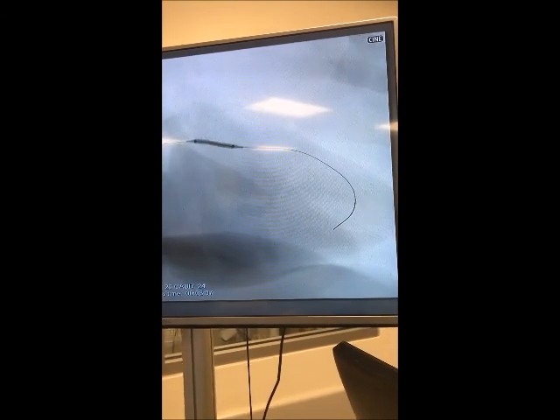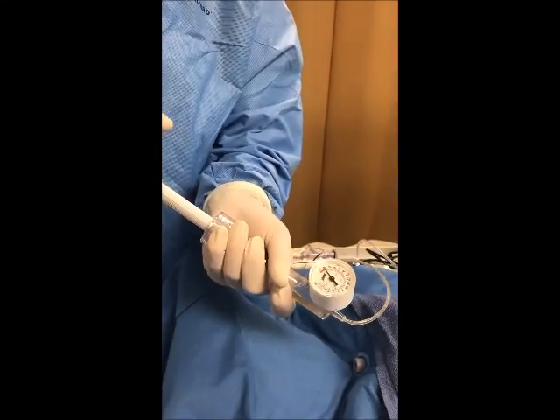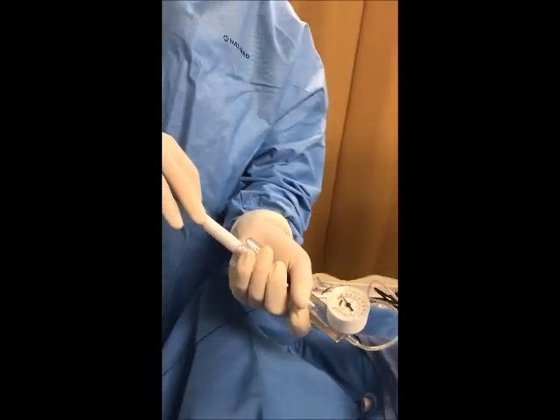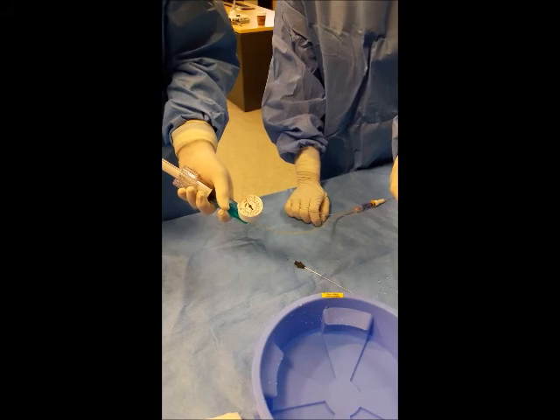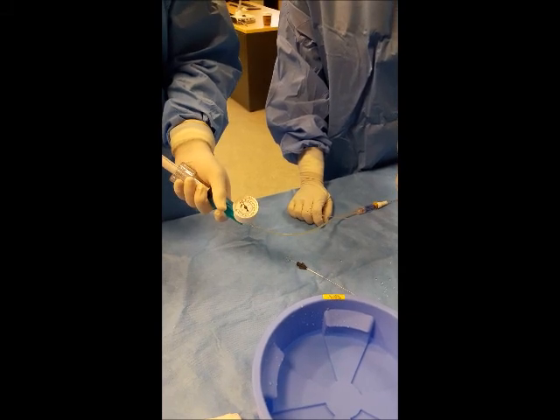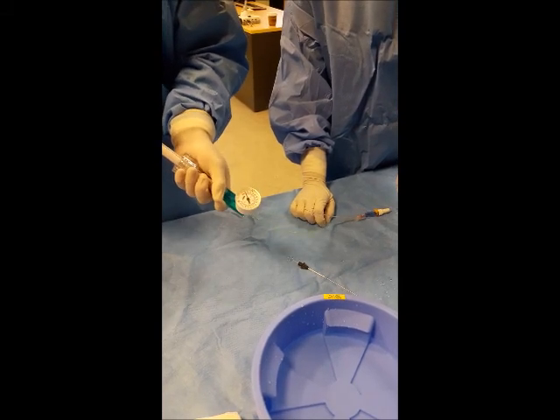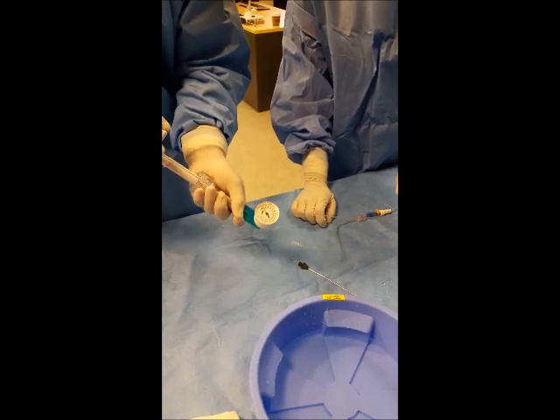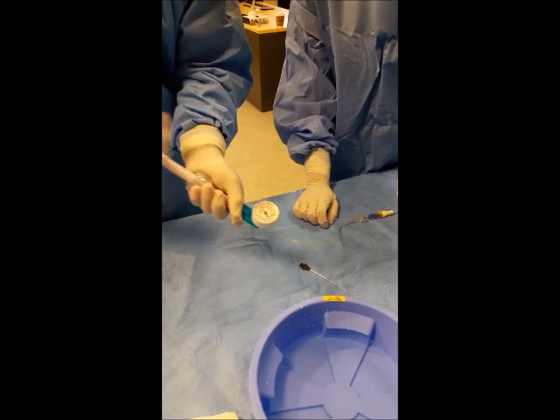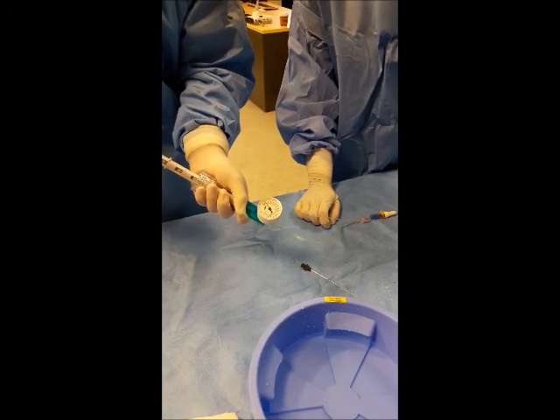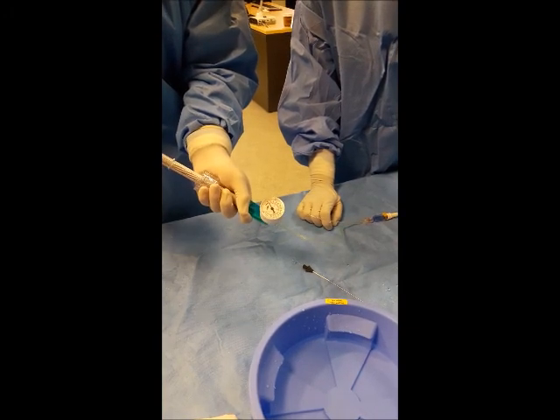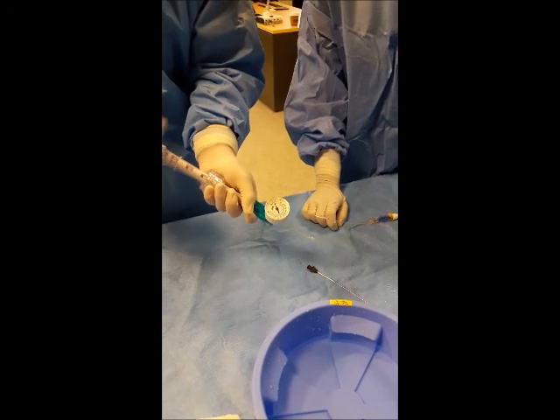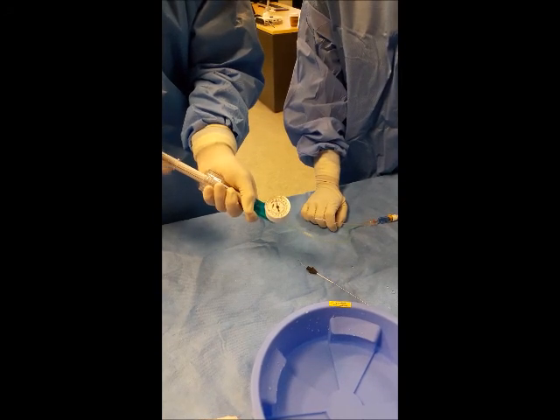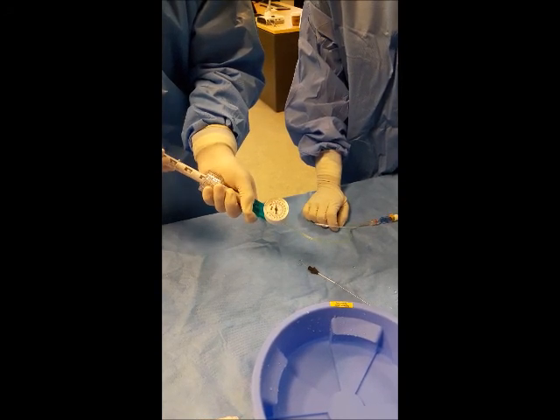First, activate your timer, then voice you are going up on the balloon and watch the monitor closely. If you have a stent, at this point you will pull negative, and then for either one, release the negative pressure. You turn the handle to the atmosphere pressure stated by the physician. Usually you will go up to nominal pressure stated in the device. The nominal pressure is the atmosphere in which the balloon will reach its stated diameter. The burst pressure is the pressure in which 5% of balloons will burst.